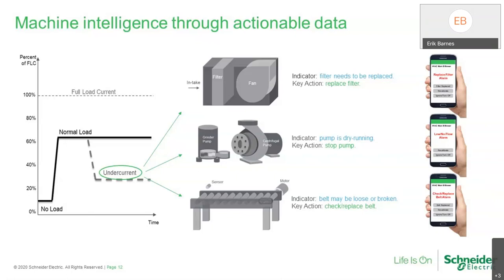Maybe you're running a conveyor. An undercurrent, depending on where you set it, can mean different things. It could mean potentially you've got a belt broken, or maybe it's loose. Or you could set it to where, hey, I don't have any load on this conveyor. Maybe I want to turn it off, or maybe I want to use that information to communicate to the PLC to make sure it's routing more items down this particular conveyor that's not being utilized very well. There are all kinds of ways you can take this.